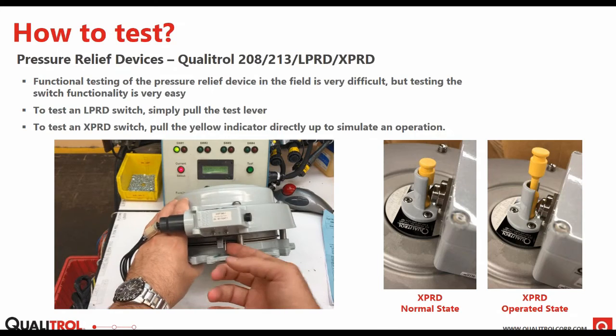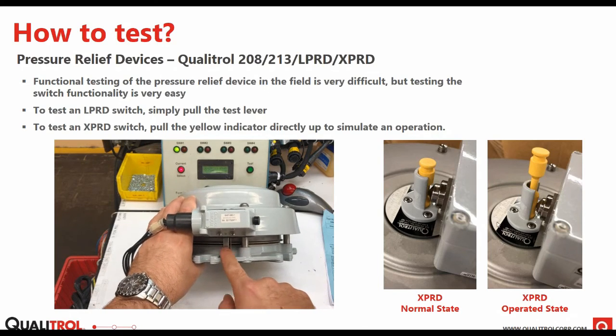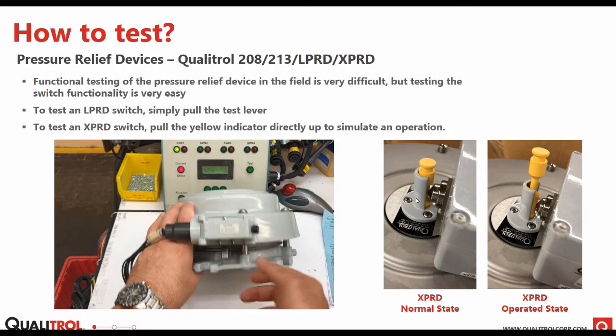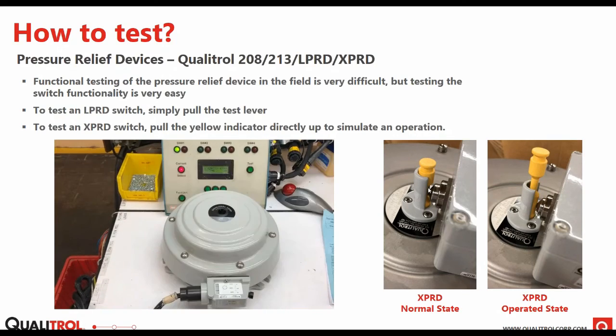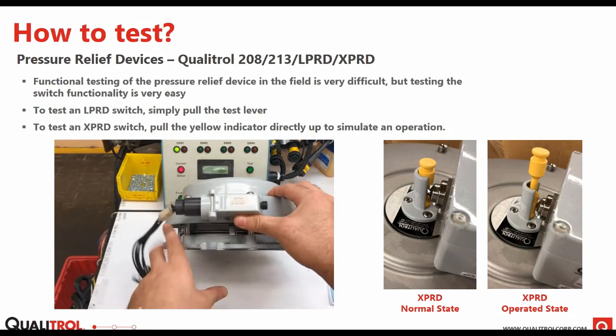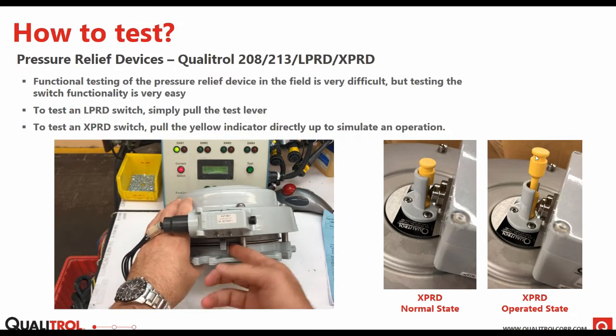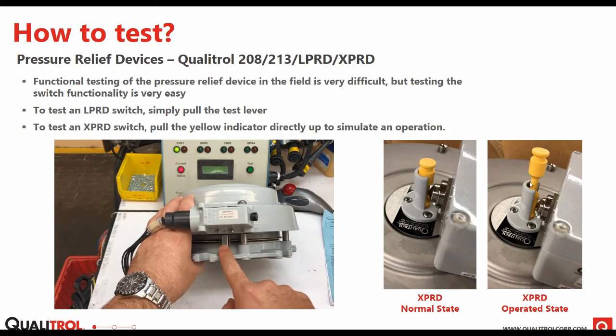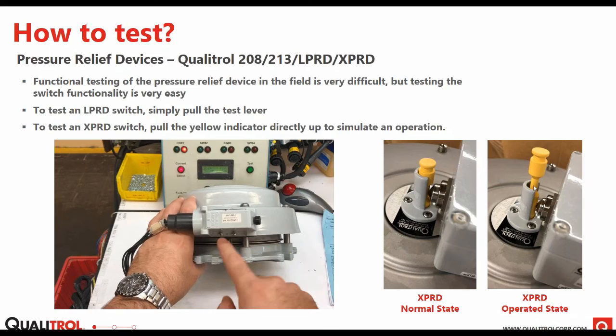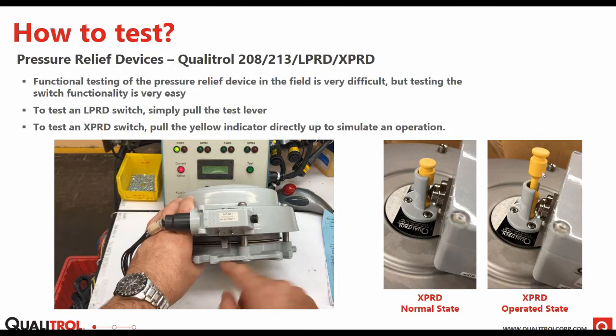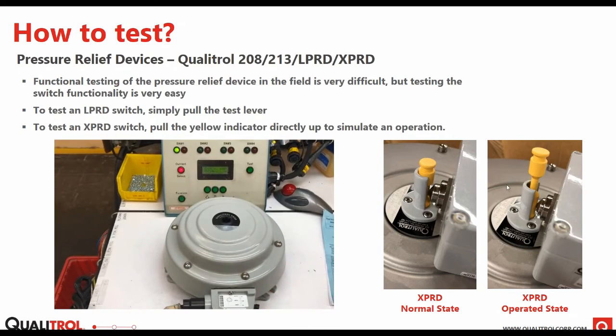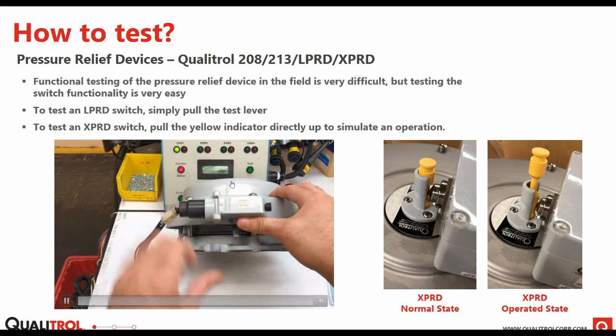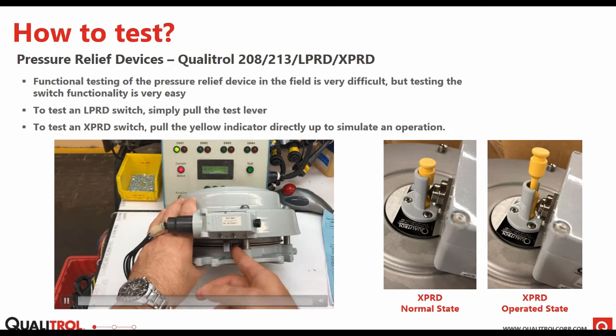Testing our XPRD is just as easy. Here are a couple of pictures of an XPRD. This is the top of the XPRD, and you can see the switch on the right side here. In the normal state, the switch plunger is in this little recess on the indicator of the XPRD. To test the XPRD, all you need to do is pull the indicator directly up. Be careful not to bend it, and pull it directly up, and that will actuate the switch. That'll simulate this XPRD actuating and pushing this indicator up. So those are two quick field ways to test our pressure relief devices that we offer, both the LPRD and the XPRD.